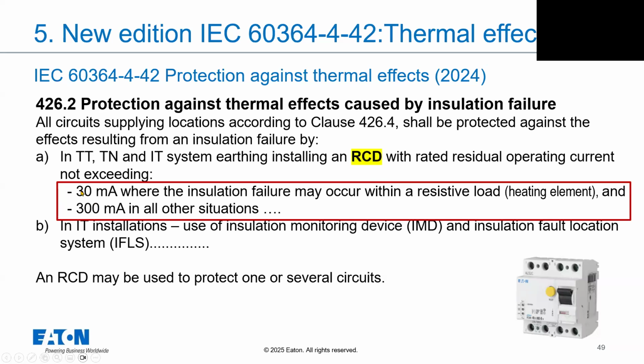Additionally, there is mention of the case of insulation failure, in situations like a heating element on ceiling and so on, which is a little bit extended against the current version. And additionally, in IT systems or IT network systems, there is a need to use an insulation monitoring device and insulation fault location system.